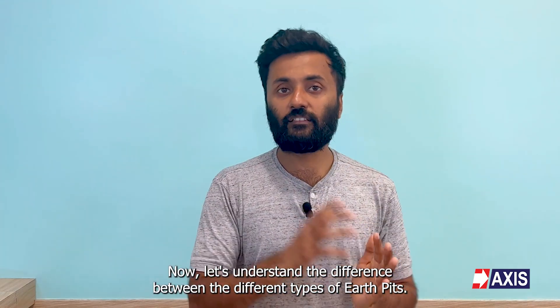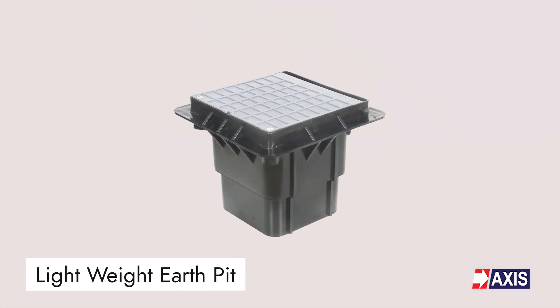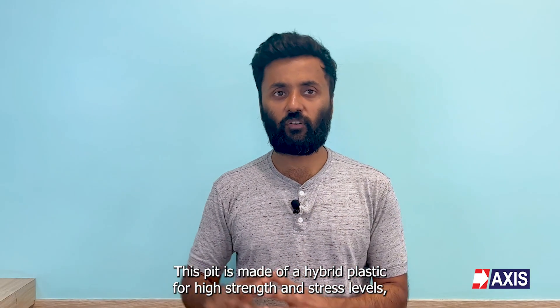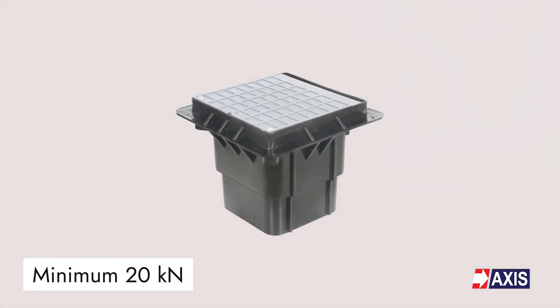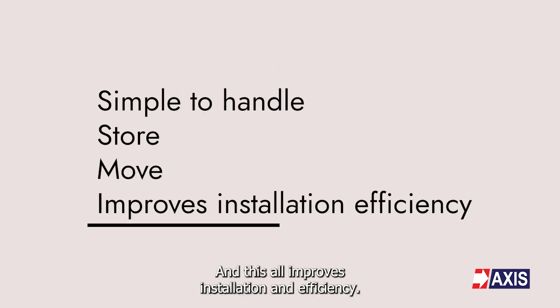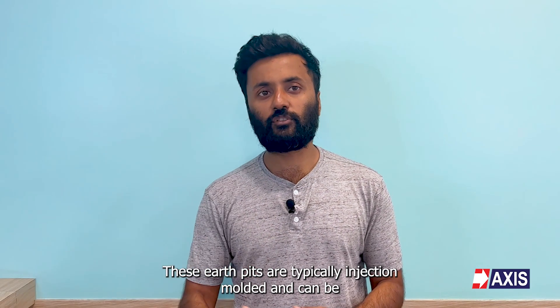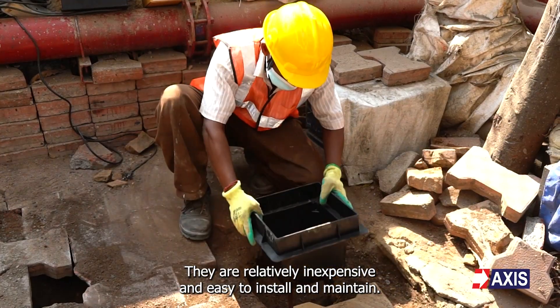Now let's understand the difference between the different types of earth pits. First of all, we have the lightweight plastic earth pit. This pit is made of a hybrid plastic for high strength and stress levels, allowing it to withstand a maximum load of 2000 kilograms. The lightweight design makes it easy to handle, store, and move, improving installation efficiency. These earth pits are typically injection molded and can be produced in a wide range of shapes and sizes. They are relatively inexpensive and easy to install and maintain.